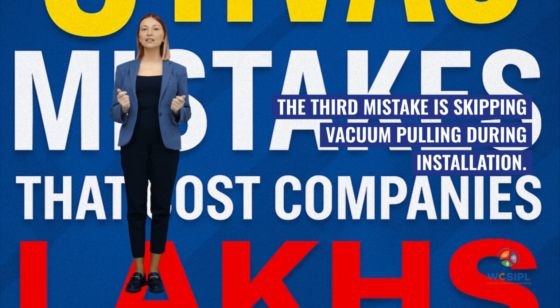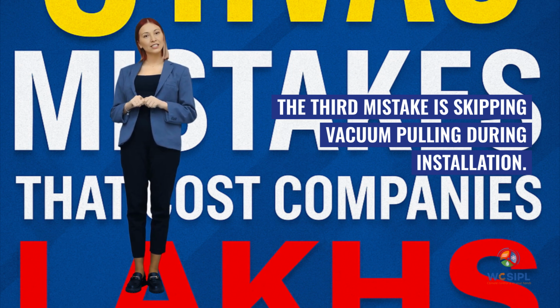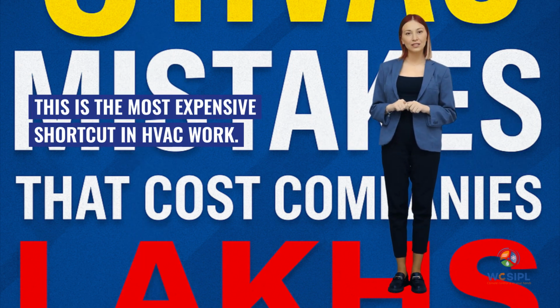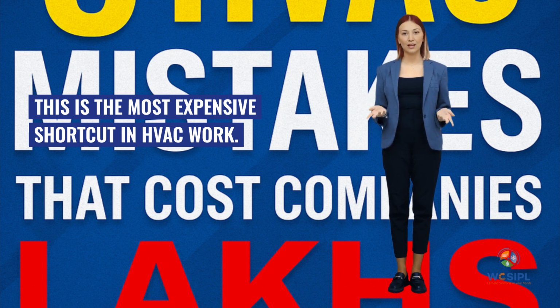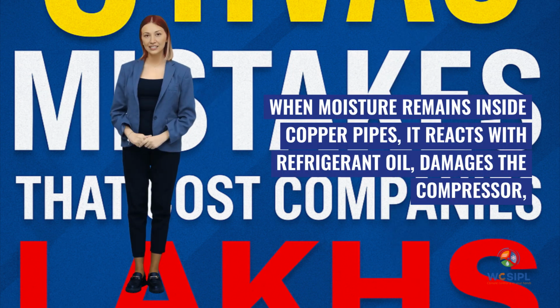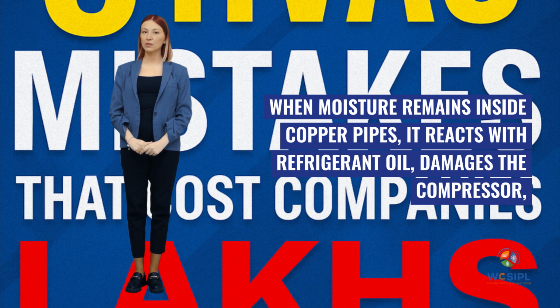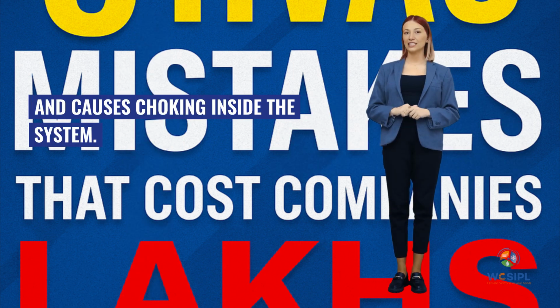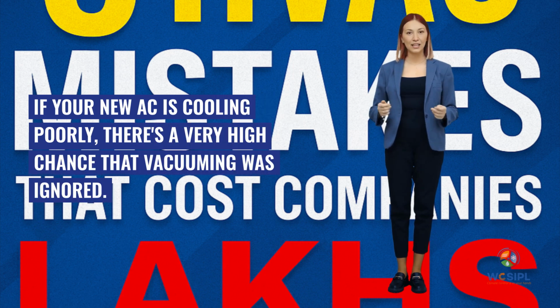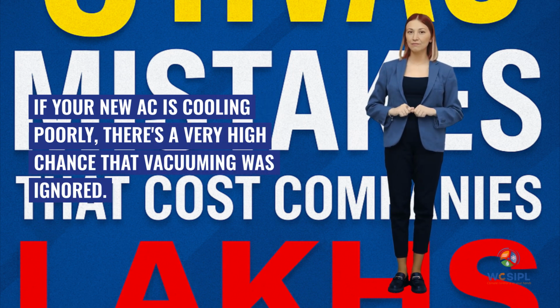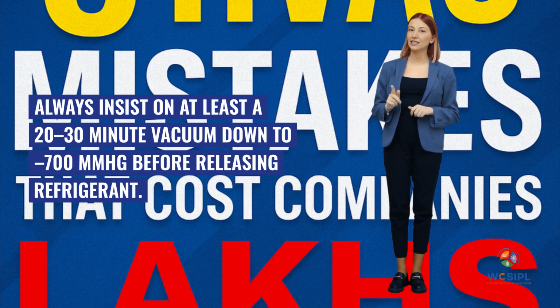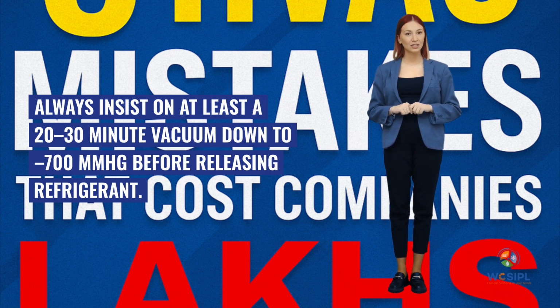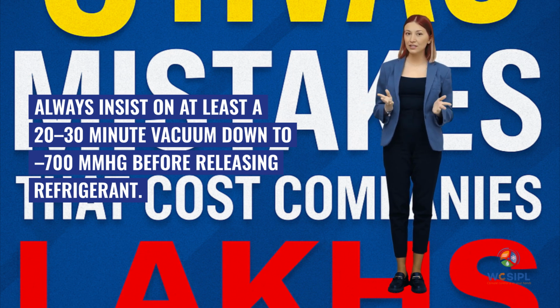The third mistake is skipping vacuum pulling during installation. This is the most expensive shortcut in HVAC work. When moisture remains inside copper pipes, it reacts with refrigerant oil, damages the compressor, and causes choking inside the system. If your new AC is cooling poorly, there's a very high chance that vacuuming was ignored. Always insist on at least a 20 to 30 minute vacuum down to -700 millimeters of mercury before releasing refrigerant.